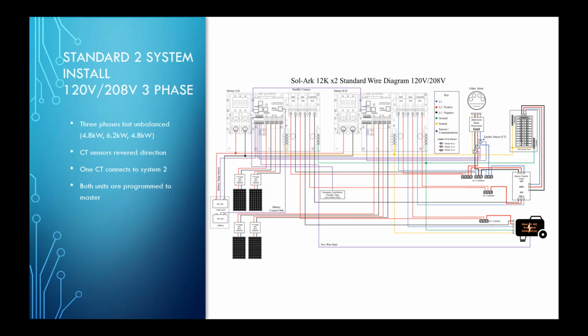As you can tell, whenever we go to 4-wire in terms of the 3-phase, because we do work with 120/208 3-phase Y. Unfortunately, Delta is a little bit different. So if you do have projects using 3-phase Delta, please give us a call and we can discuss maybe some possible solutions. But in this case, we'll focus on the 208Y connections. So really here, you'll notice that both systems are labeled master. There is not a slave unit at this time unless you get past 6 systems.